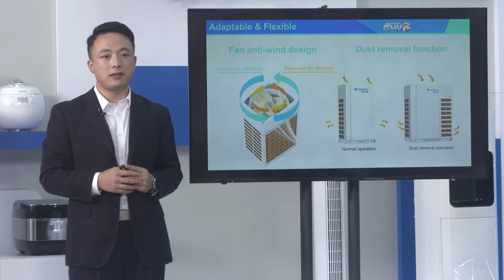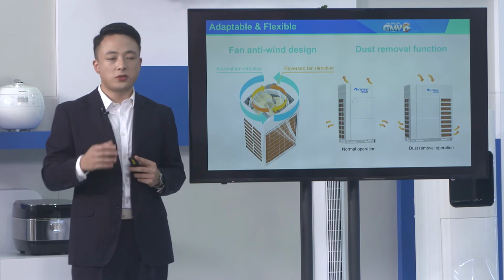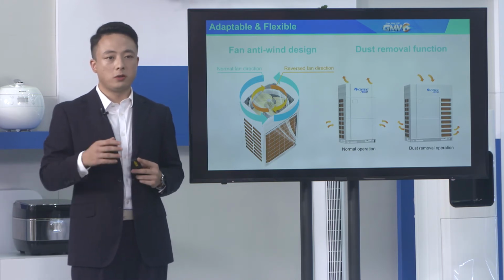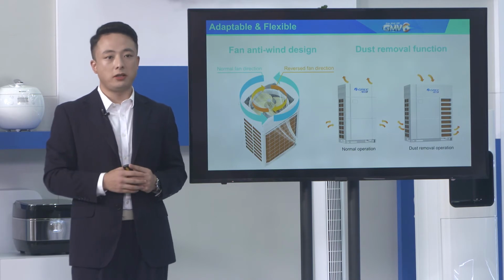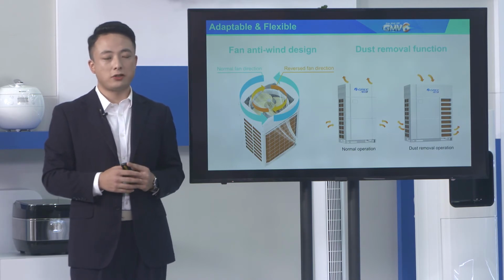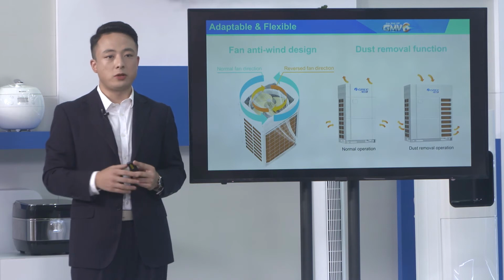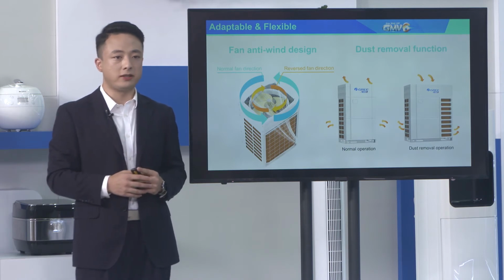When used in the desert area, dust easily gets into the outdoor unit. We use a dust removal function, which allows the units to automatically remove the dust when the heat exchanger is dusty. It has greatly improved the heat exchange rate.